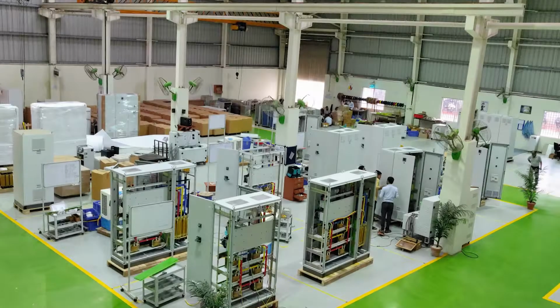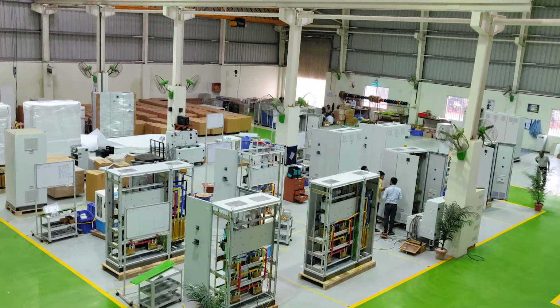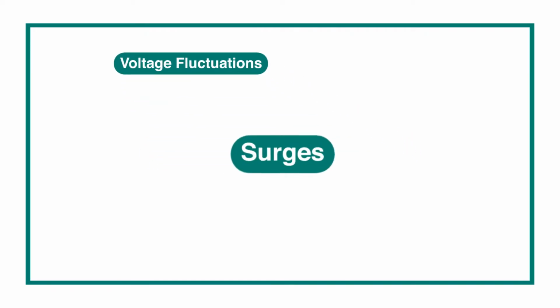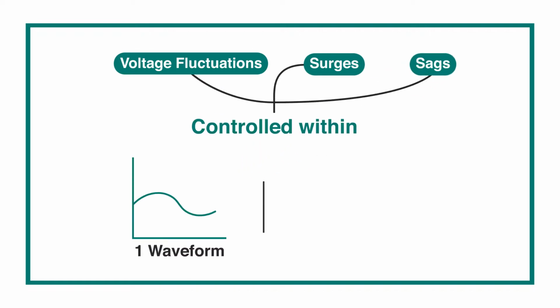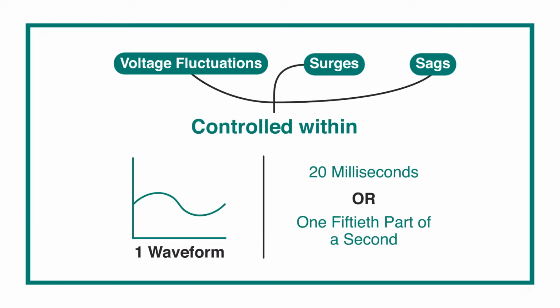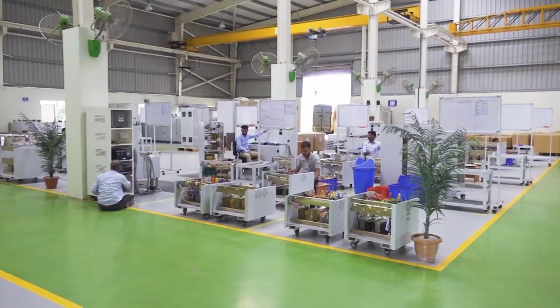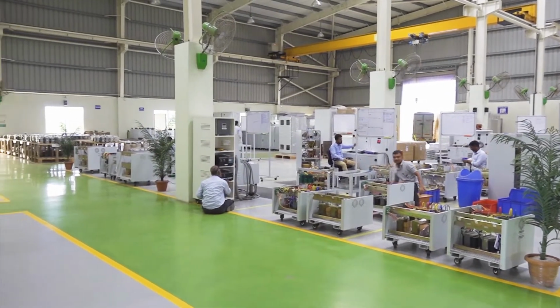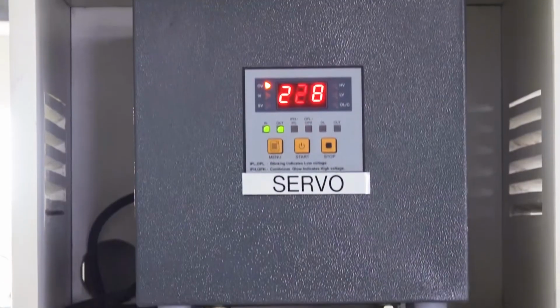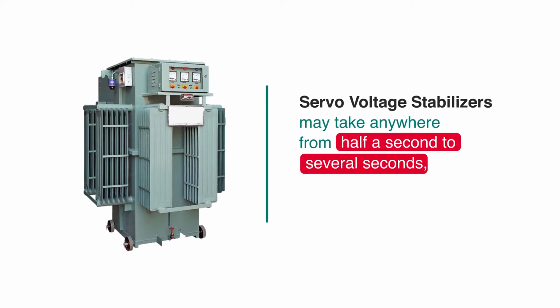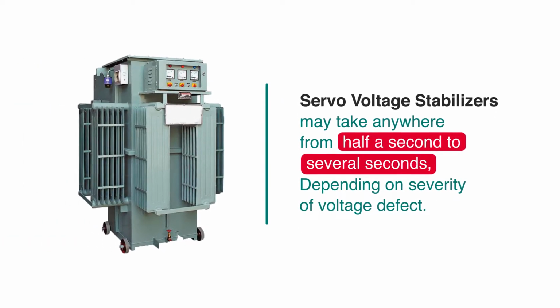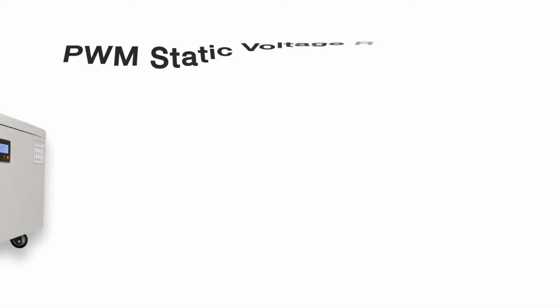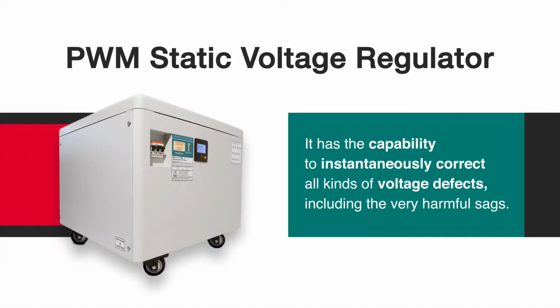The foremost demand of electronics is high quality of power, where any sudden voltage fluctuations, surges, sags are controlled within one waveform, that is, 20 milliseconds or 1/50th part of a second. This is easier said than done by conventional technologies of servo voltage stabilizers or tap-changing transformers, because these may take anywhere from half second to several seconds depending on severity of voltage defect. The ideal solution is a static voltage regulator which has the capability to instantaneously correct all kinds of voltage defects, including the very harmful sags.